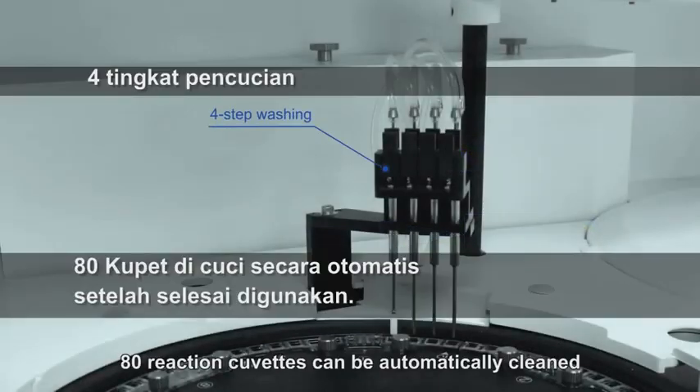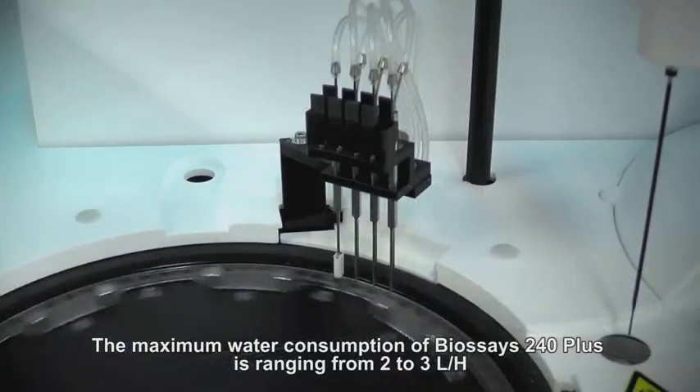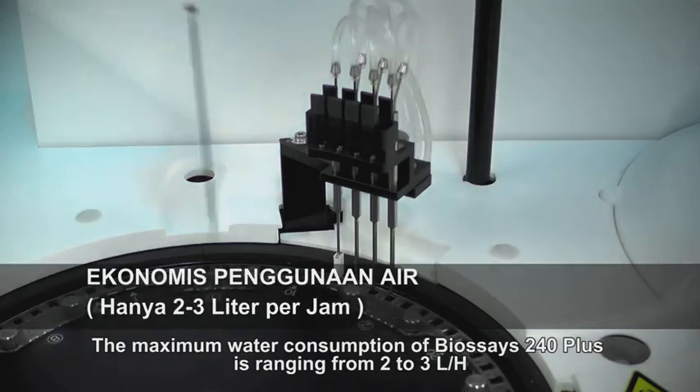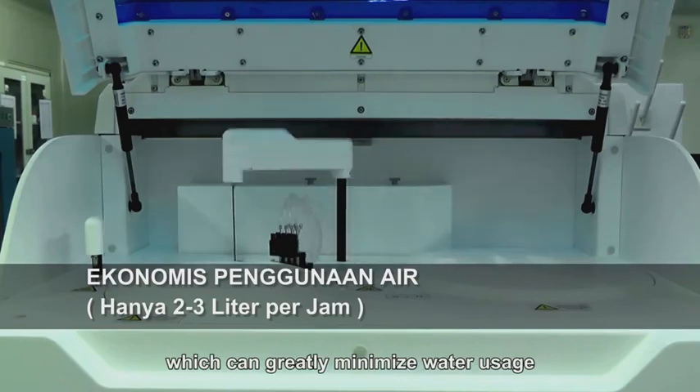80 reaction cuvettes can be automatically cleaned by a station with a 4-step washing procedure. The maximum water consumption of Biossays 240 Plus ranges from 2 to 3 liters per hour, which greatly minimizes water usage.